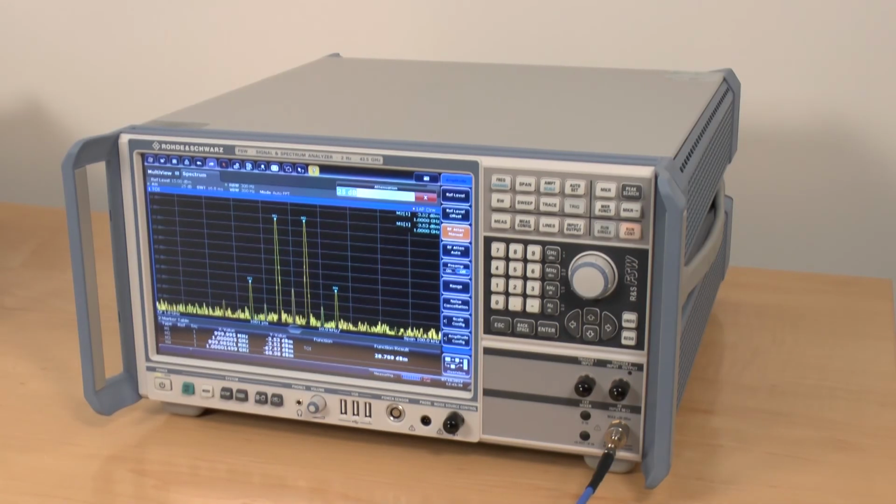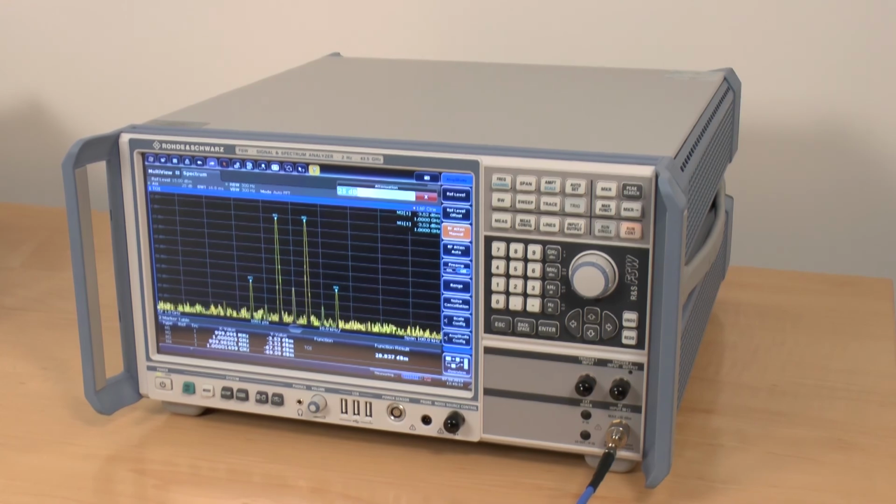Using a spectrum analyzer to measure phase noise is the easiest method and the one that gives the fastest and very accurate results, but it is always best to double check the setup and make sure all the right precautions have been taken.